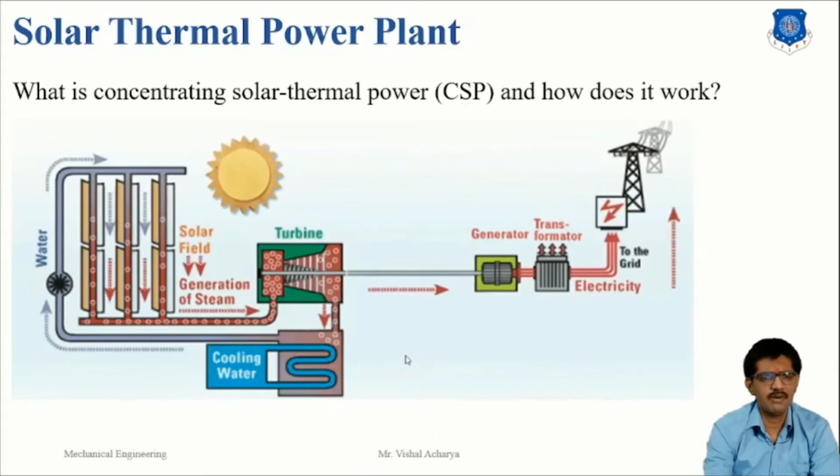Concentrating solar thermal power plant systems are generally used as utility scale projects. These utility scale projects can be considered in different ways. Power tower systems arrange mirrors around a central tower that acts as a receiver. Linear systems have rows of mirrors that concentrate the sunlight onto parallel tube receivers positioned above them. The smaller power plant systems can be located directly where power is needed. For example, a single dish system can produce 5 to 25 kilowatts of power per dish and be used as a distributed application.